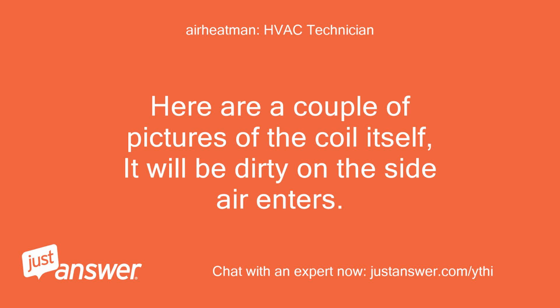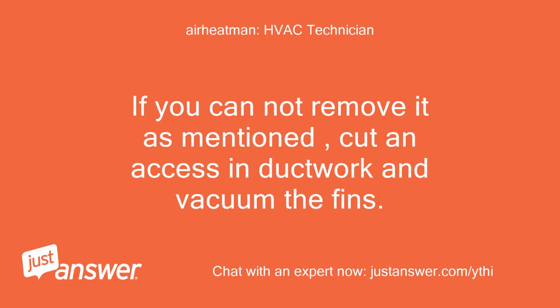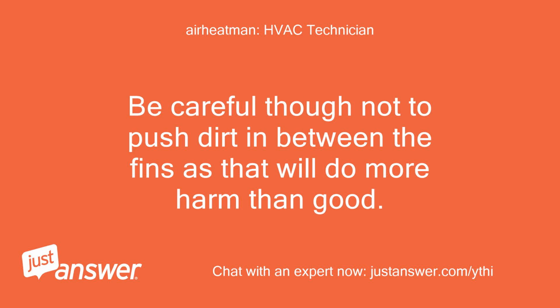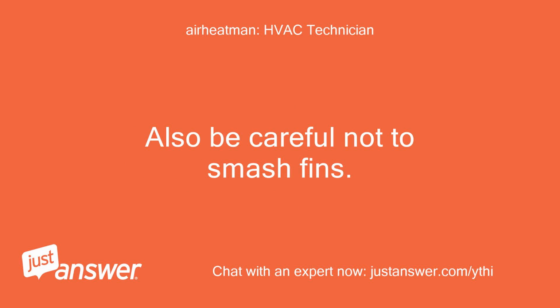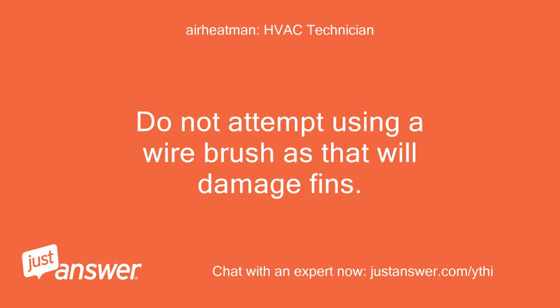Here are a couple of pictures of the coil itself. It will be dirty on the side air enters. If you cannot remove it as mentioned, cut an access in ductwork and vacuum the fins. Be careful though not to push dirt in between the fins, as that will do more harm than good. Also be careful not to smash fins. Do not attempt using a wire brush, as that will damage fins.